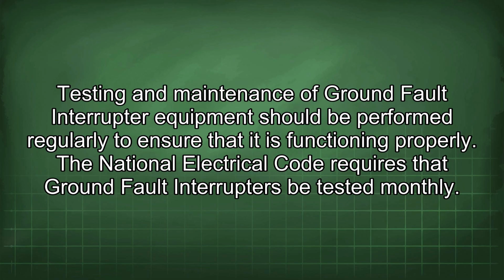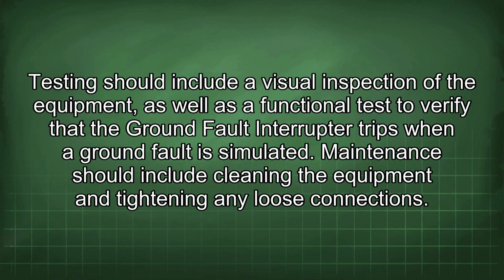Testing and maintenance of ground fault interrupter equipment should be performed regularly to ensure that it is functioning properly. The National Electrical Code requires that ground fault interrupters be tested monthly. Testing should include a visual inspection of the equipment, as well as a functional test to verify that the ground fault interrupter trips when a ground fault is simulated. Maintenance should include cleaning the equipment and tightening any loose connections.